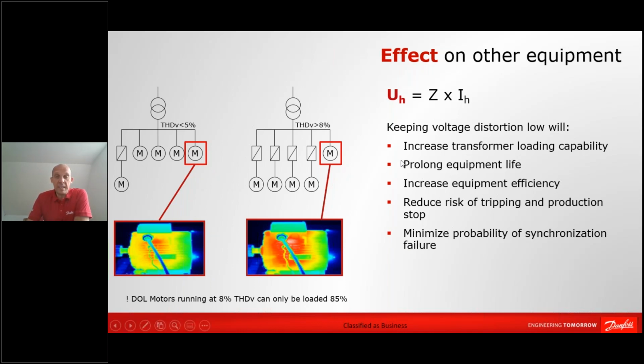There is actually an IEEE standard saying how much you're allowed to load your motor when you have a given amount of voltage distortion. You can find some curves in the standard, and the curve actually tells you that if you have 8% voltage distortion, you shouldn't load your direct online motor with more than 85%. And of course, if you have 10%, that number has dropped down to 75%.